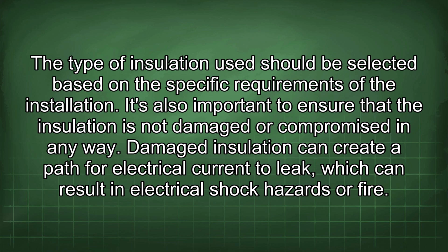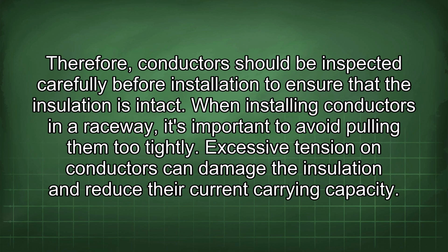It's also important to ensure that the insulation is not damaged or compromised in any way. Damaged insulation can create a path for electrical current to leak, which can result in electrical shock hazards or fire. Therefore, conductors should be inspected carefully before installation to ensure that the insulation is intact.